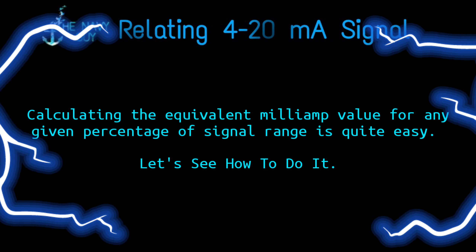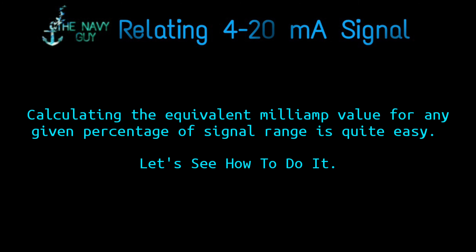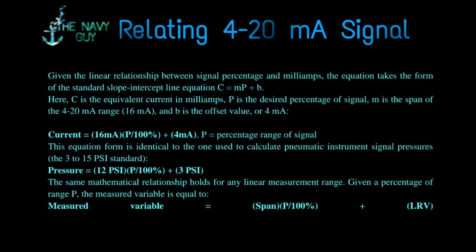Calculating the equivalent milliamp value for any given percentage of signal range is straightforward. Given the linear relationship between signal percentage and milliamps, the equation takes the form of the slope-intercept line equation: C = m × p + b, where C is the equivalent current in milliamps, p is the desired percentage of signal, m is the span of the 4 to 20 mA range (16 mA), and b is the offset value of 4 mA. Therefore: Current = (16 mA × p / 100%) + 4 mA. This form is identical to the pneumatic equivalent: Pressure = (12 psi × p / 100%) + 3 psi.